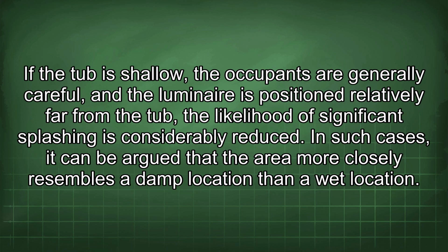If the tub is shallow, the occupants are generally careful, and the luminaire is positioned relatively far from the tub, the likelihood of significant splashing is considerably reduced. In such cases, it can be argued that the area more closely resembles a damp location than a wet location.